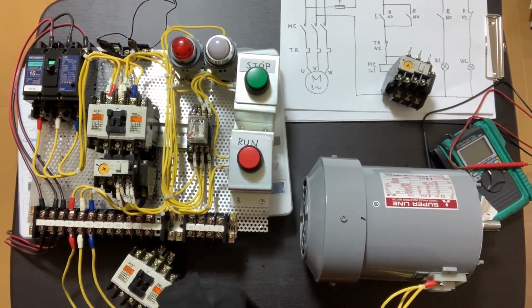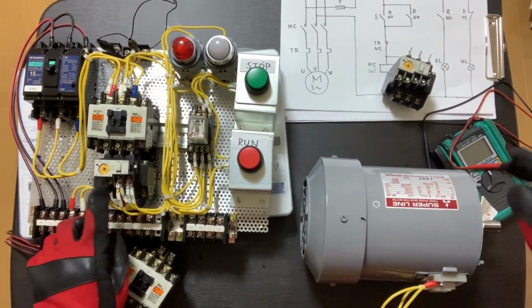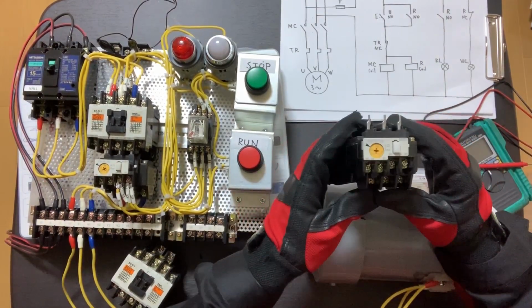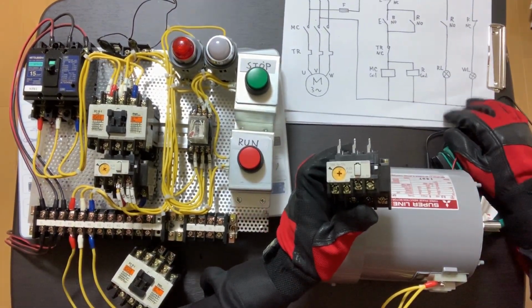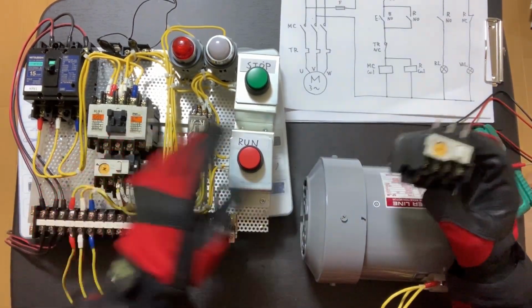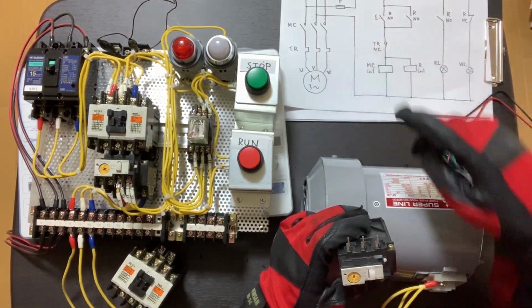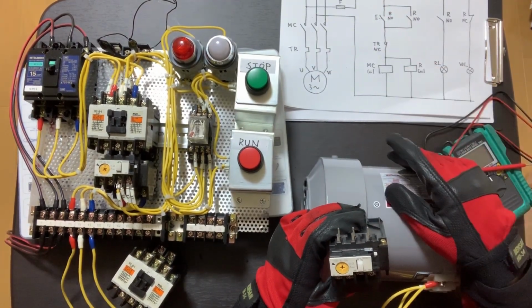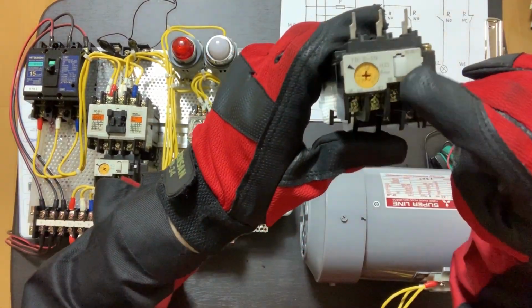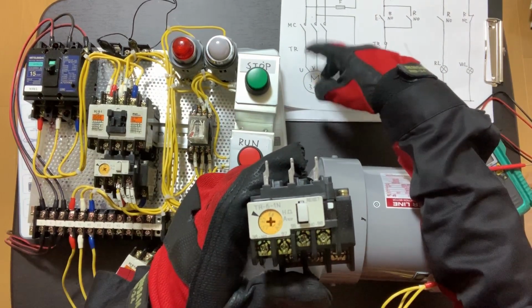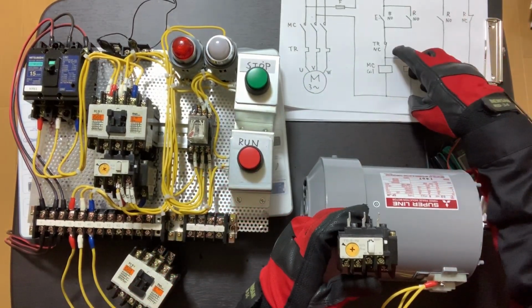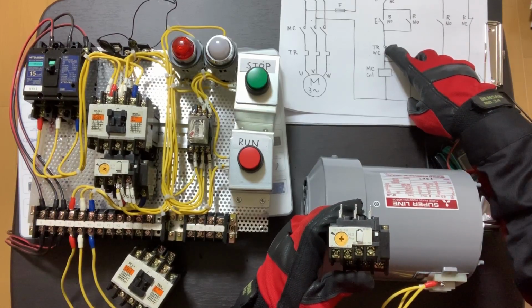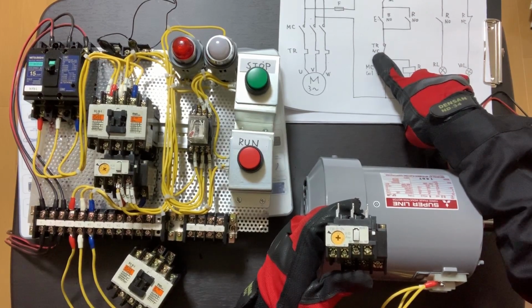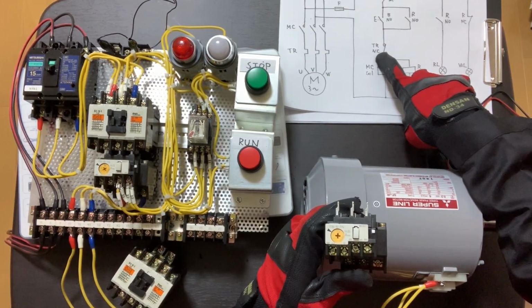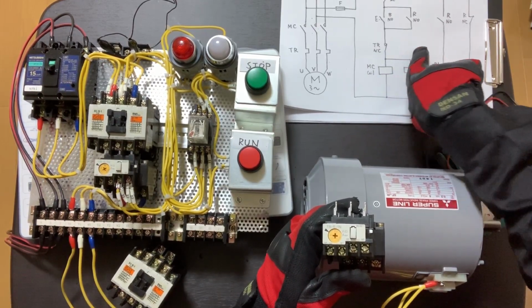the thermal protection relays have a closed and open contact, same as a magnetic contactor, and when the load current exceeds its setting value, in this case this is 2.1 ampere. So if the load current reaches 2.1 ampere, each contact will flip, and in this case it's a normally closed contact, so this contact will turn to open circuit.